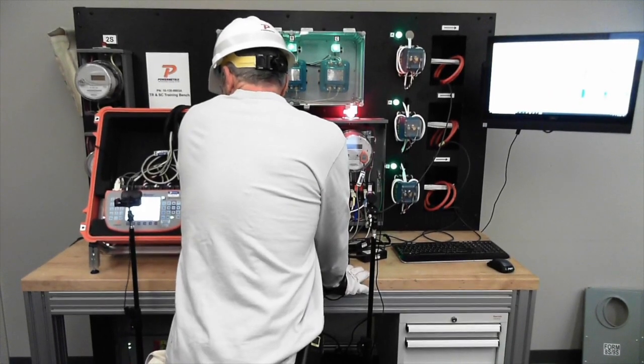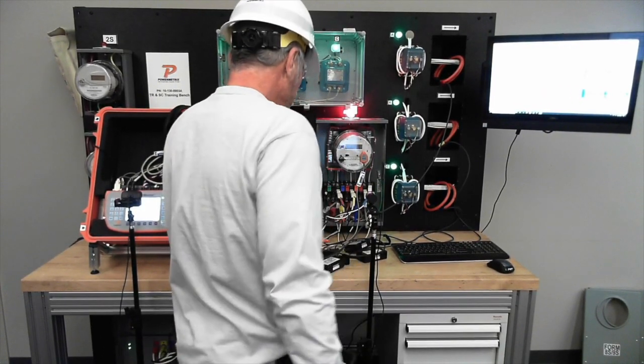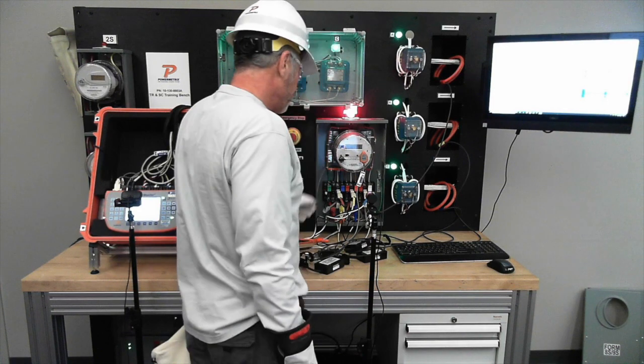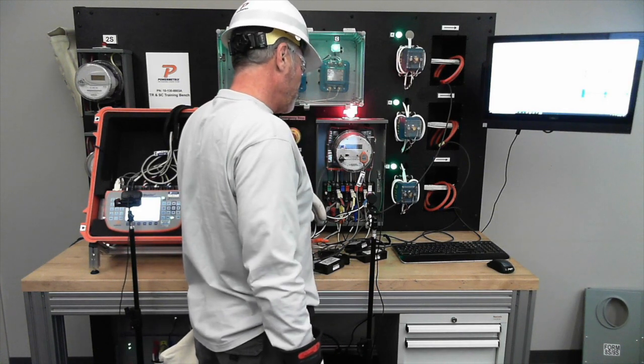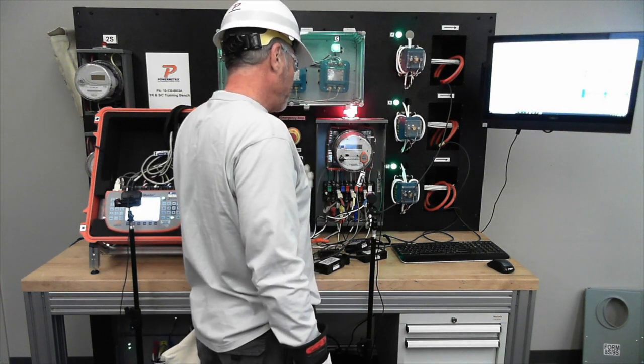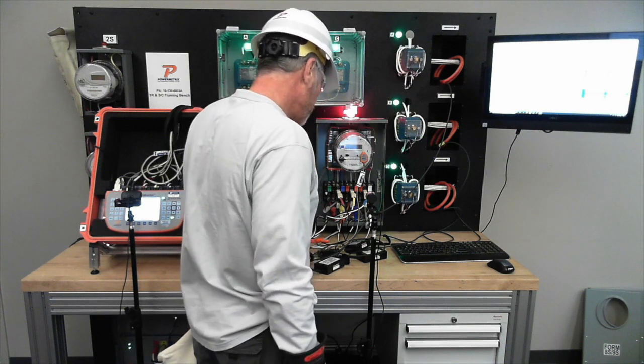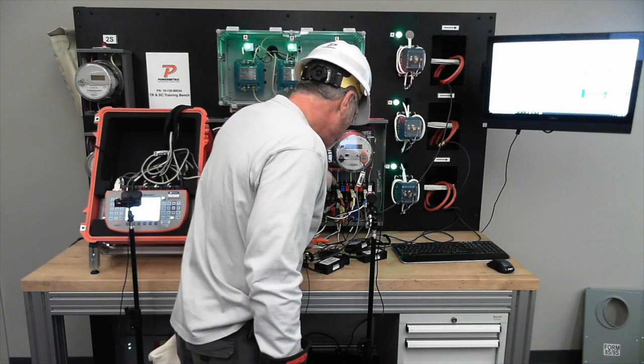But then it should tell me, remember we've done these before on these webinars, it's different when I get ready to go from the customer load to the phantom load, because now I'm using the load box, so I'm taking the CTs out of it. So the very first move I make is to open up these shunts.